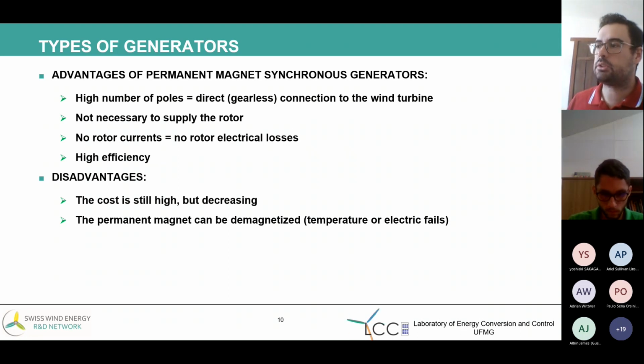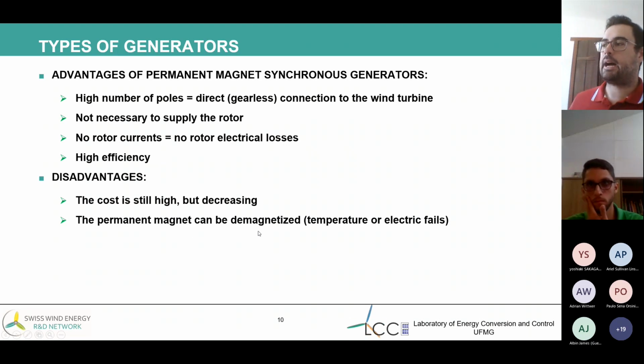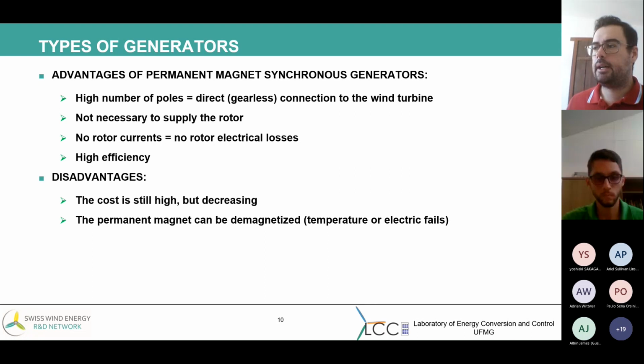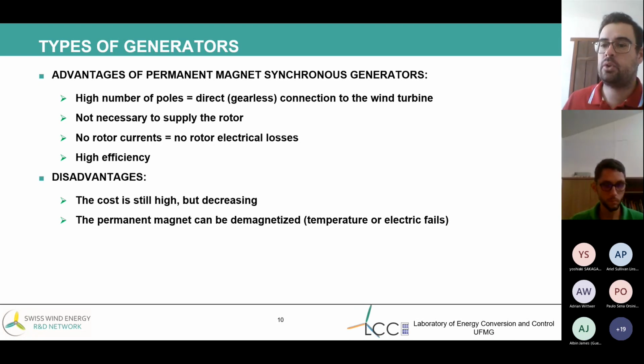The permanent magnet can be demagnetized by temperature or electric failures, mainly by temperature. Overheating of the machine can destroy the machine and can demagnetize the permanent magnet. If one permanent magnet is demagnetized, the generator is useless. It's necessary to disassemble and construct it again, so it's maintained. It's very complicated. Alvin?